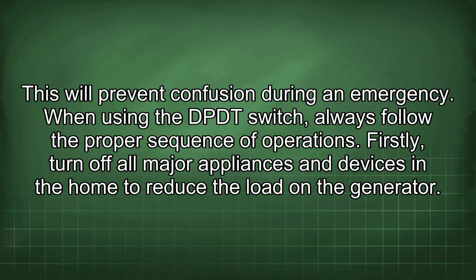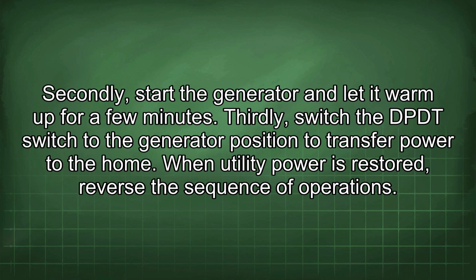When using the DP-DT switch, always follow the proper sequence of operations. Firstly, turn off all major appliances and devices in the home to reduce the load on the generator. Secondly, start the generator and let it warm up for a few minutes. Thirdly, switch the DP-DT switch to the generator position to transfer power to the home. When utility power is restored, reverse the sequence of operations.